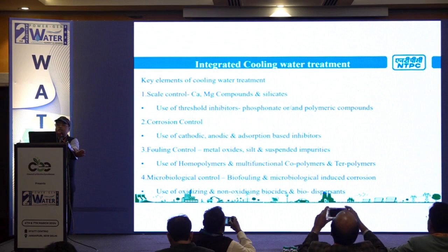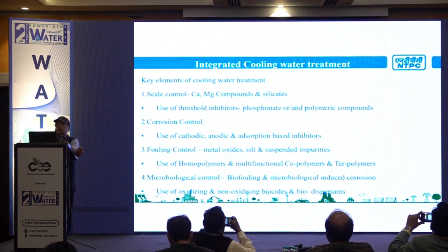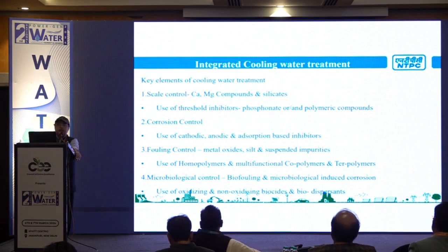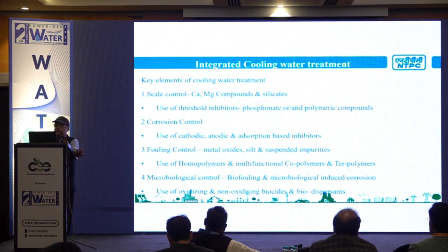So we have adopted an integrated cooling water treatment program: scale control for calcium and magnesium, using threshold inhibitors for phosphonate and phosphate base - we use PBTC and organophosphate. For corrosion control, we use zinc based inhibitors. For fouling control, we use biodispersants.